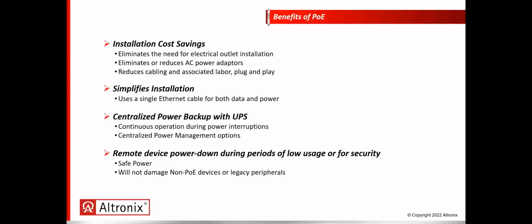So what are some of the benefits of PoE? There's installation cost savings. It eliminates the need for an electrical outlet in the installation right next to the device, or eliminates or reduces the AC power adapters that are needed. It also reduces cabling and associated labor. It's plug and play. So now I can run a category 6 cable or category 5E cable along the same cable trays and pathways as the regular data cables. It simplifies installation using a single Ethernet cable for both data and power.